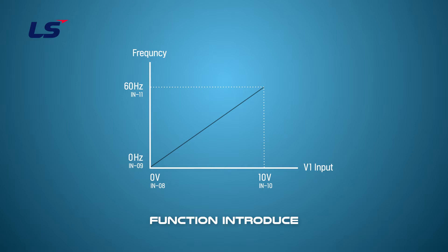It is normal operation. In some cases, you might want to stop drive until 2 volts is entered, or you might want to drive at the maximum frequency when only 8 volts is entered. In this case, you must set the frequency for the analog input.